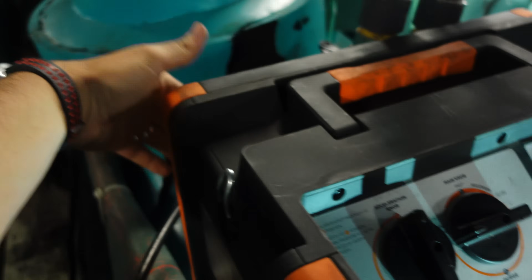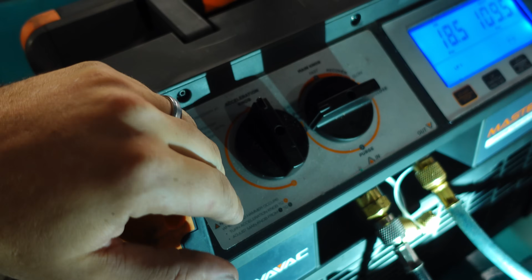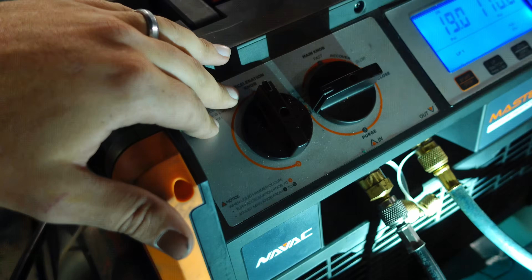And then on the AB setting of this knob, and why we got some weird numbers, if you remember back whenever we were doing the recovery and I said I was going to reach out to NAVAC and ask them about it, the B setting is supposed to be faster for vapor per their recommendations. Well, the way I was thinking about it was slightly skewed and not 100% correct. The overall design of the pump, there's actually two pumps in there, which I think a commenter even pointed out at some point. Those two pumps are piped parallel with each other. So you've got two separate ones pumping through parallel, and that's how they're able to get a 4 cylinders. Technically 2-cylinder pumps pumping side by side.